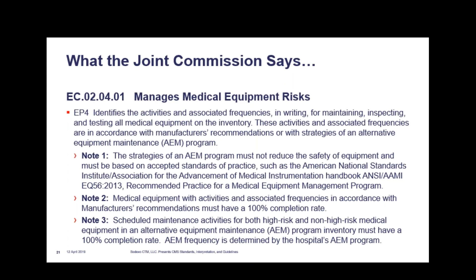Yeah, it's great. All right, so we got 10 minutes and about 10 slides left, so we're going to run through some of these. All right, what the Joint Commission says about AEMs is, again, they're great, you can use them. ANSI 56, 2013, recommended practice for medical management programs. Medical equipment with activities associated with frequency, 100%. And high risk and non-high risk must be called out. I personally think call out OEM high and low risk. I'm not even sure why we do that now, seeing how everybody has to be at 100%, other than you know what is high risk, what is non-high risk, and what requires an AEM frequency.